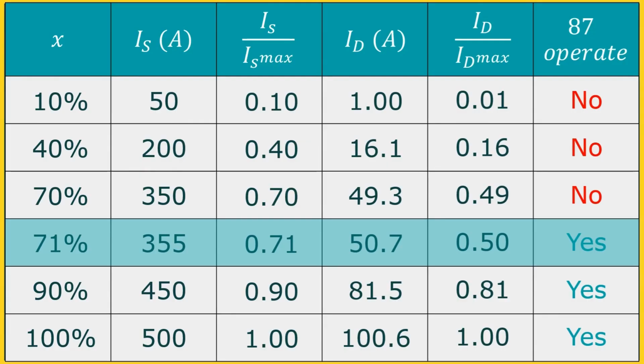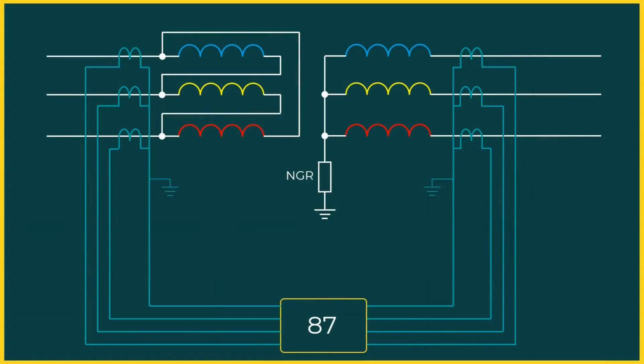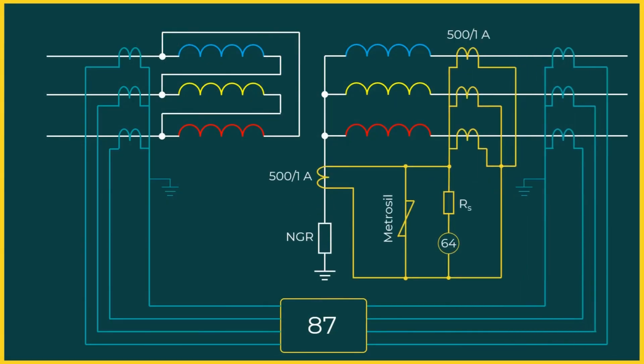So the question arises, what is the solution for this kind of problem? The solution is providing restricted earth fault protection. The REF protection does not rely on the phase currents alone. Instead, it compares the vector sum of the phase CTs with the neutral CT. If there is any imbalance between the vector sum of the phase CTs and the neutral CT, the REF relay will pick up and hence it will protect the transformer for the earth fault in the low voltage winding.